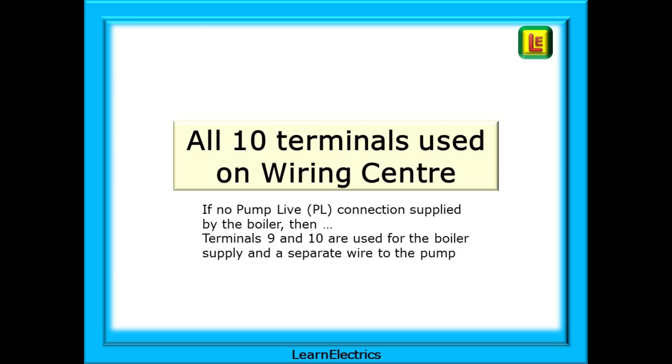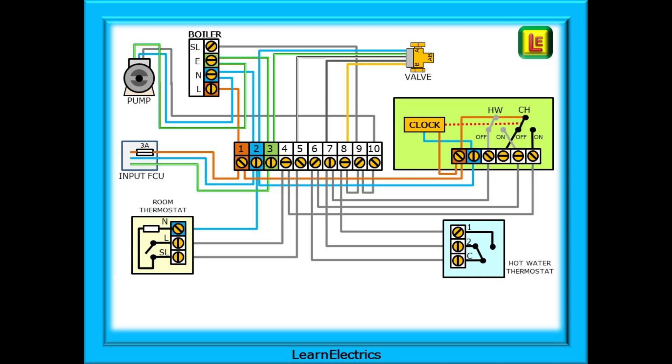Some wiring centers are supplied with and use all 10 terminals in the wiring center. If there is no pump live or PL connection on the boiler, then we may have to energize the pump from the wiring center. In this example we will link terminals 9 and 10 to terminal 8 and use these for the boiler and the pump separately. This is shown on this slide. The orange wire goes to terminal 8. This is linked to 9 and then to 10. 9 goes to the boiler and 10 goes to the pump. One disadvantage of this method is that there is no overrun for the pump.